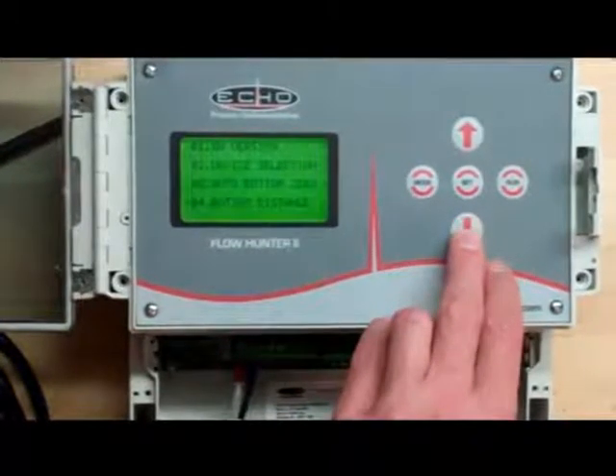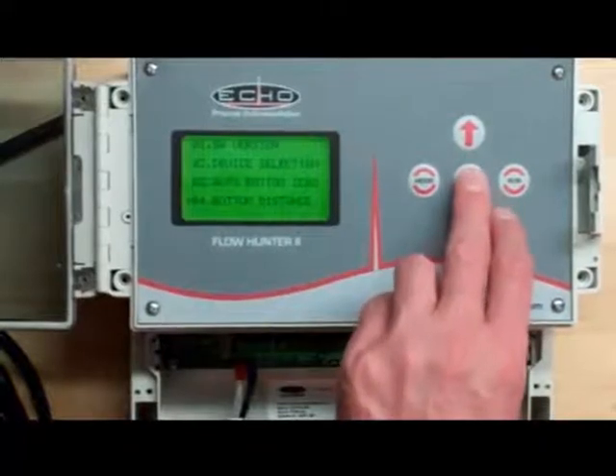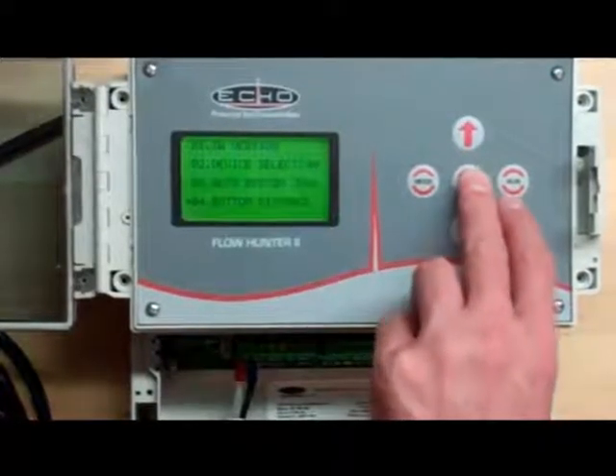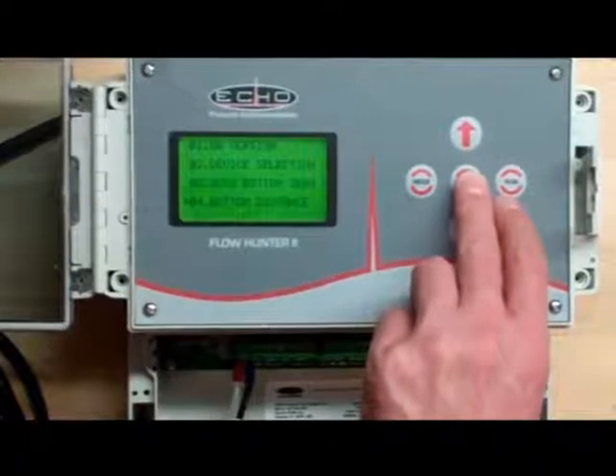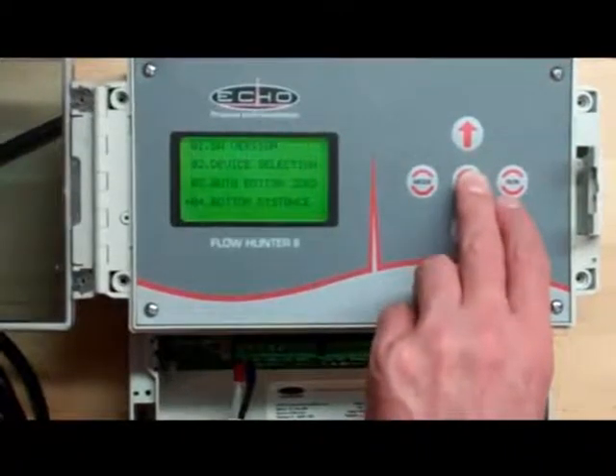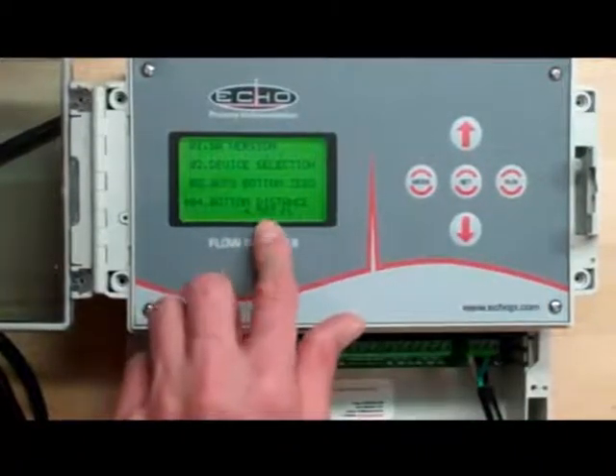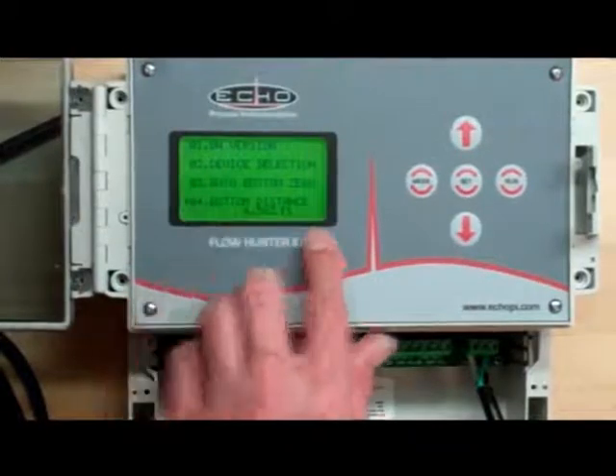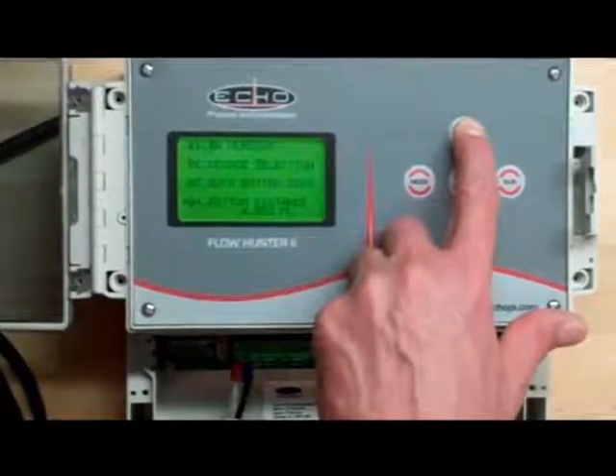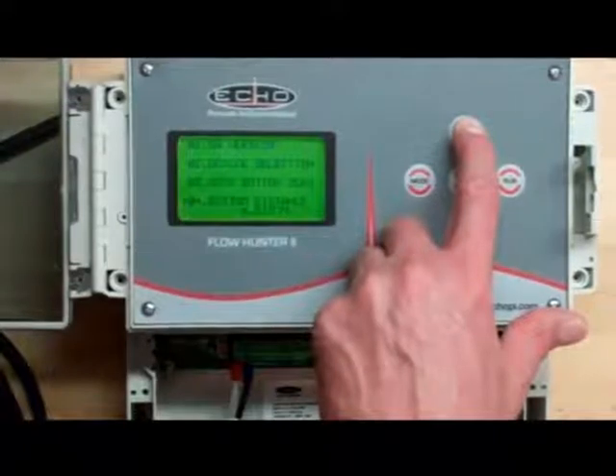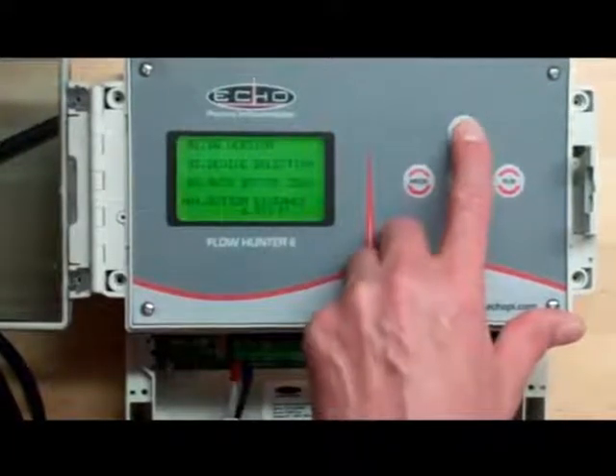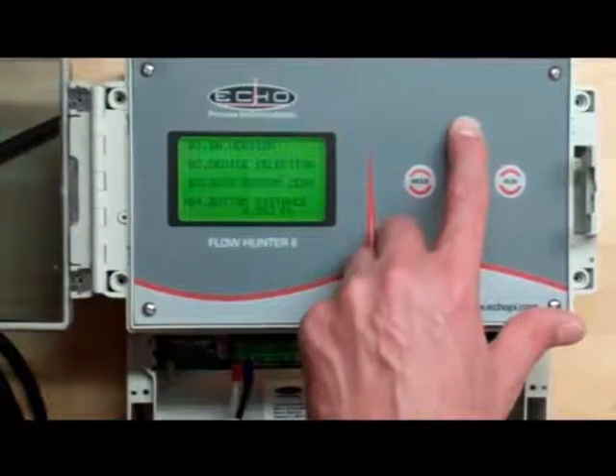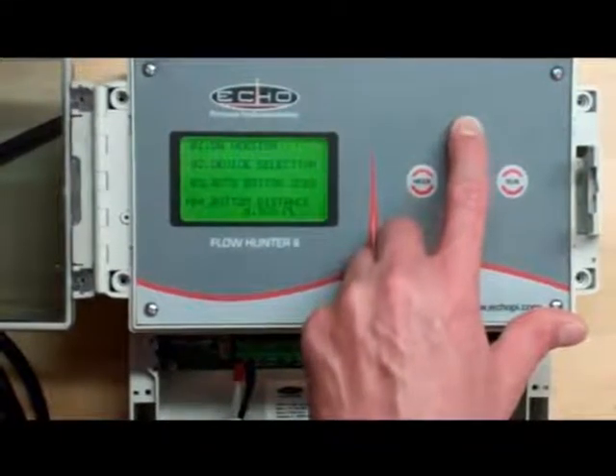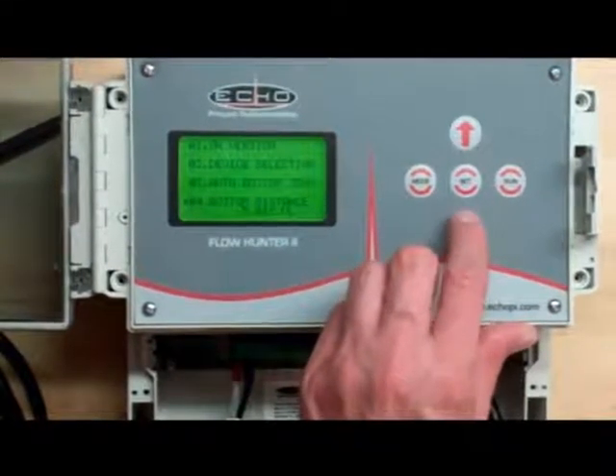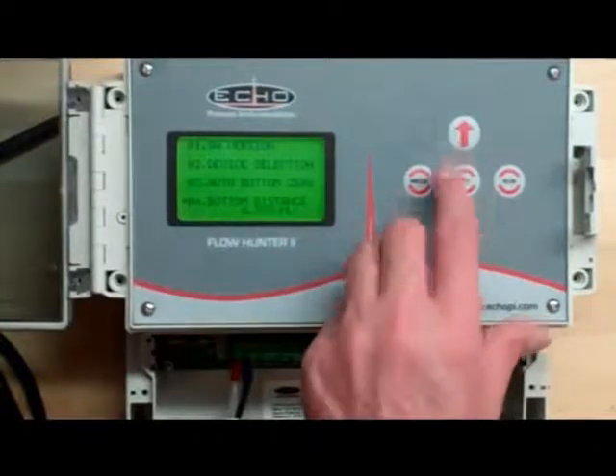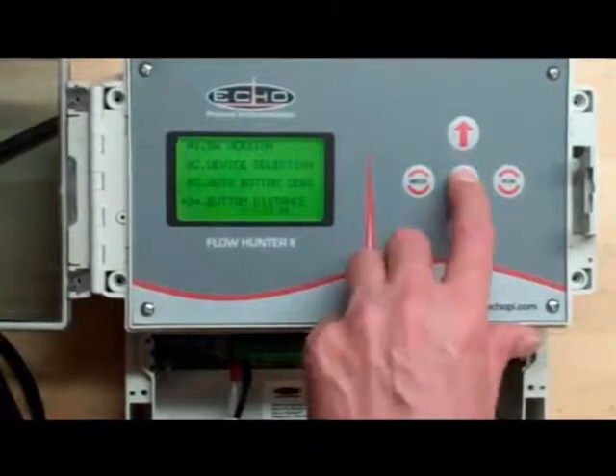Now we're going to go down to number 4, which is bottom distance. This is when you manually want to select your bottom distance or empty distance. Of course, earlier we did the 4.5 for the auto bottom. We're going to change that. I'm going to move it up to about 5 feet. Hold the up button until we get there. Once we're at 5 feet, we hit set to save.